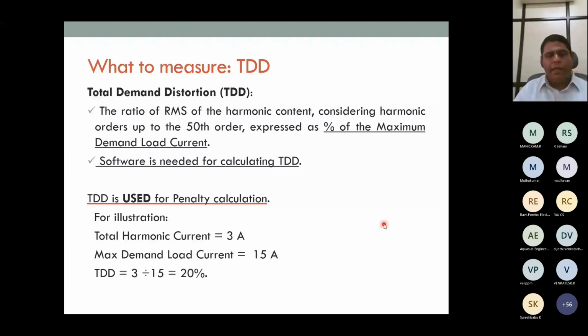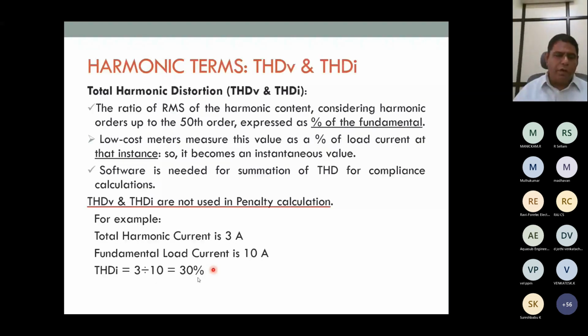The difference between the earlier harmonic regulations and what is currently practiced from 2014 onwards, based on IEEE 2014, is the way TDD is calculated. For example, for 3 amps of harmonic current where the total maximum demand current is 15 amps, it will be 20%. In the earlier case, it was measured differently: they were taking the fundamental load current and arriving at 30%. It's almost 10% more.